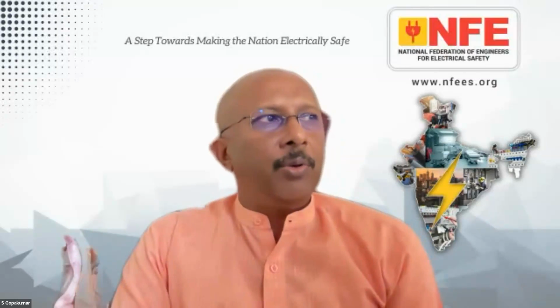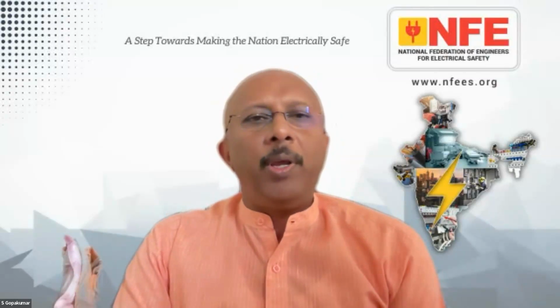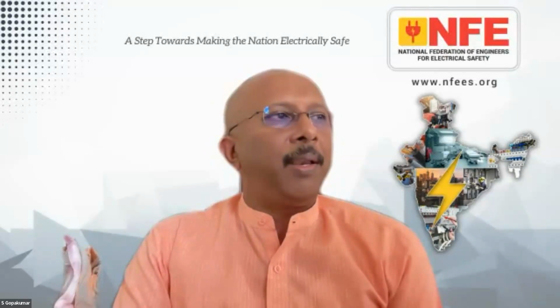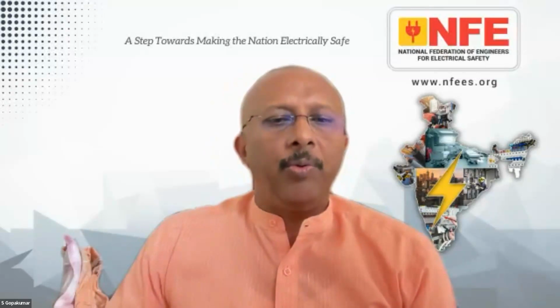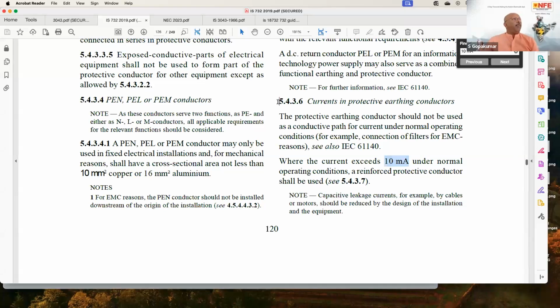So what you can do is go to clause number 5.4.3.6 of IS 732, or let me just show you. You see here, 5.4.3.6, currents in protective conductor. That means due to leakage, there is some current in the conductor. Where the current exceeds 10 milliampere under normal condition, a reinforced protective conductor shall be used.